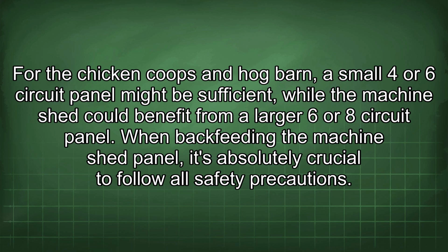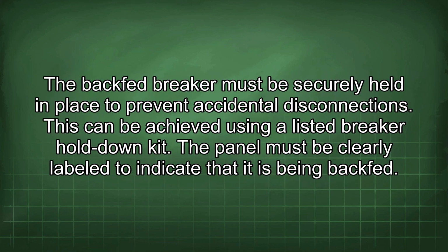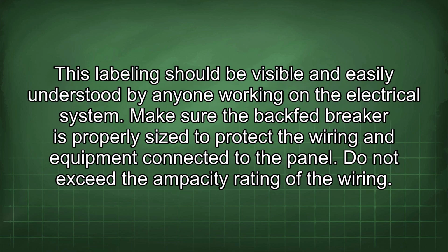When backfeeding the machine shed panel, it's absolutely crucial to follow all safety precautions. The backfeed breaker must be securely held in place to prevent accidental disconnections. This can be achieved using a listed breaker hold-down kit. The panel must be clearly labeled to indicate that it is being backfed. This labeling should be visible and easily understood by anyone working on the electrical system.